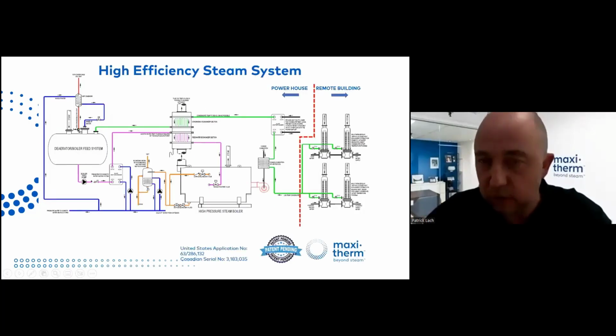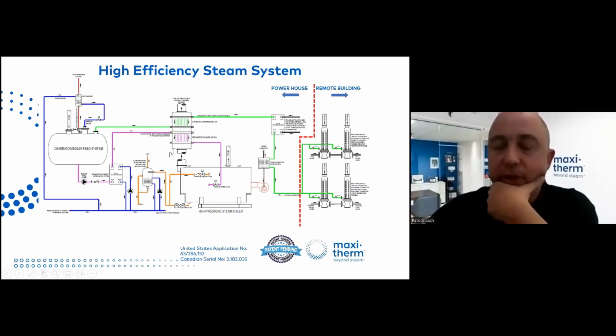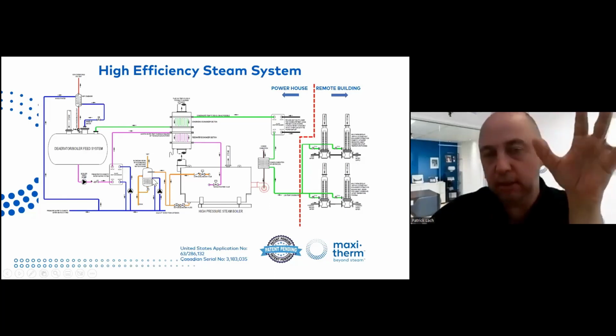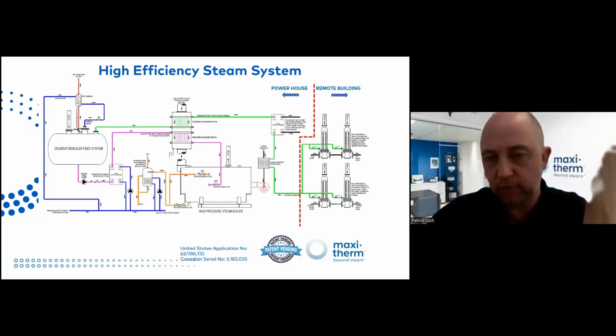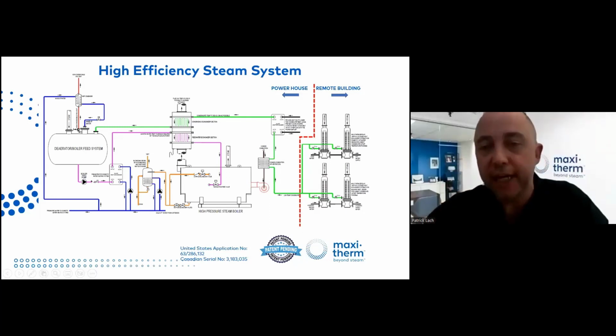So the concept is multiple units of Maxi-Therm or flooding design in your building, campus, city, whatever, factory, and you're returning 100% condensate closed loop. So all we did basically is all those technologies you see, air preheater on the burner, condensing stack economizer, heat recovery on the vent condenser or the blowdown or whatever, all this, it's proven technology, right? It's all proven technology. So all we patent is all the ingredients together, okay? The cake, basically, like Tony always says. So the goal is to return cold condensate as possible.